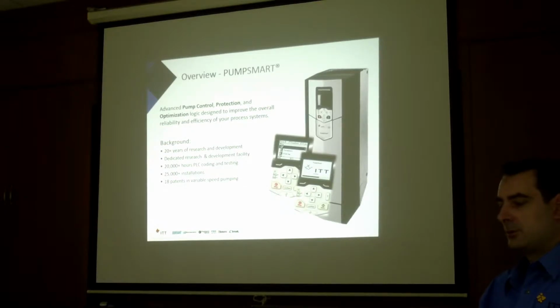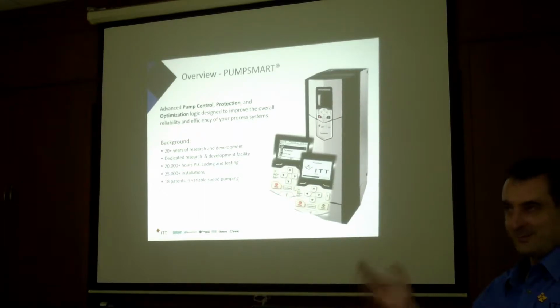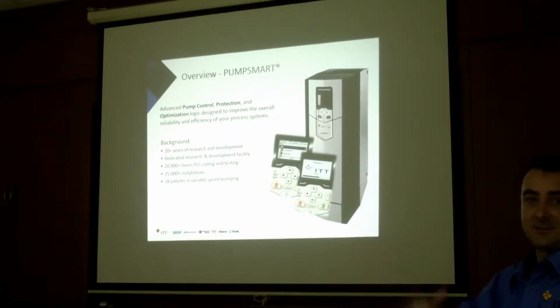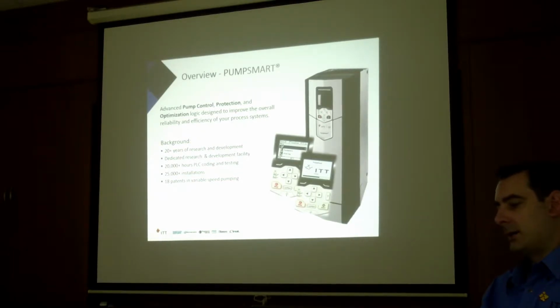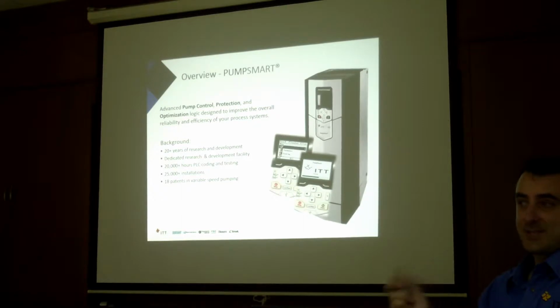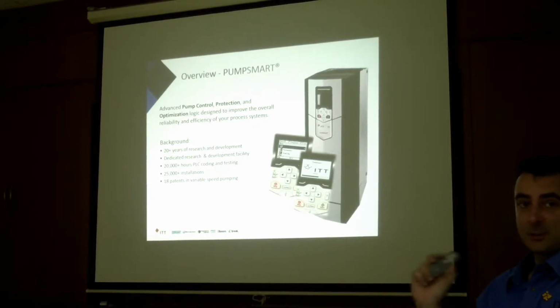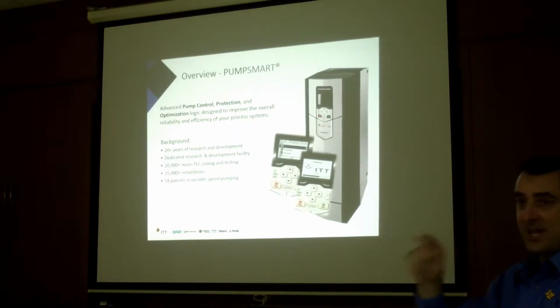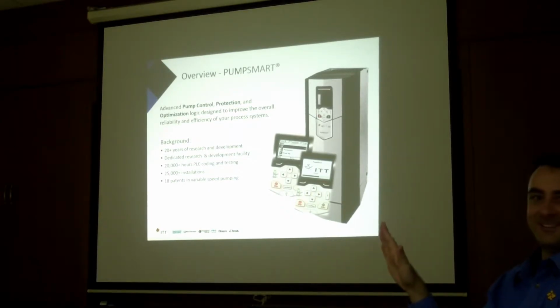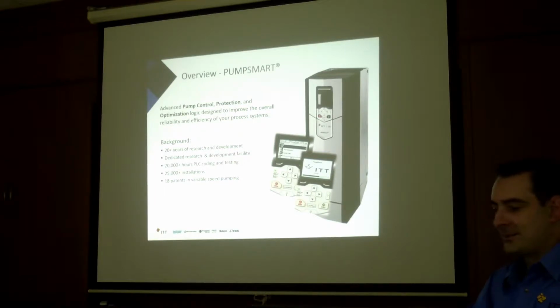Because I have a good understanding of how many hours it takes to code a PLC. When they code a PLC, often it's very simple, whereas ours is very complex but very easy to get in there. So it actually saves them time. As a comparison, I think we could code a normal tank terminal arrangement, maybe take 300 hours of coding. If the customer uses our system properly, maybe they can do it in 10 hours of coding. Start, stop, that's it. On and off. Everything else can be done by the pump smart.